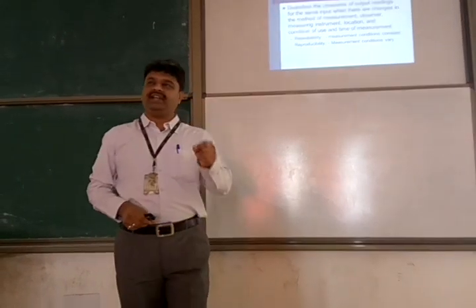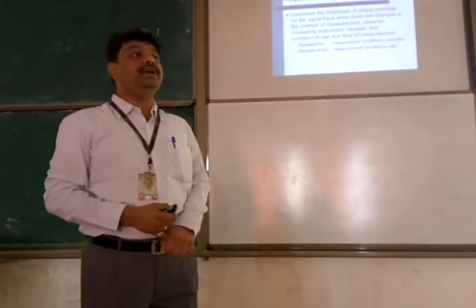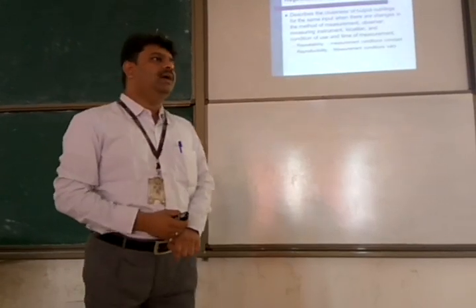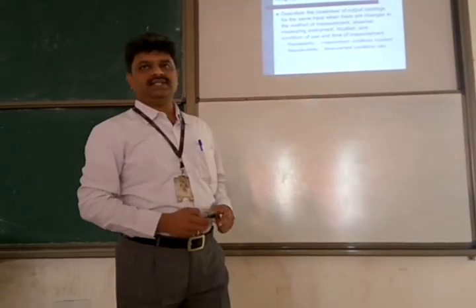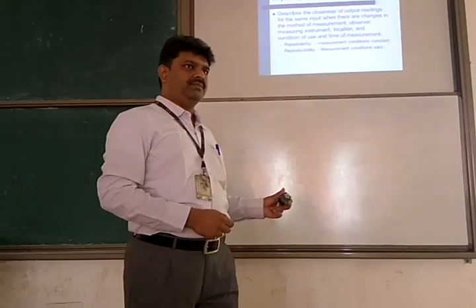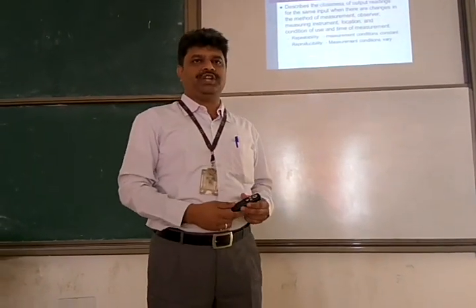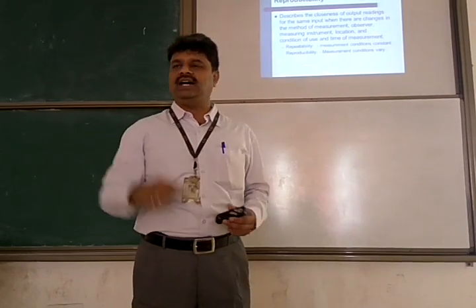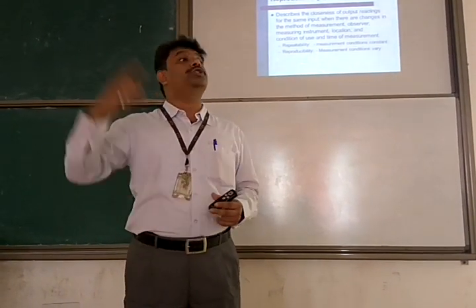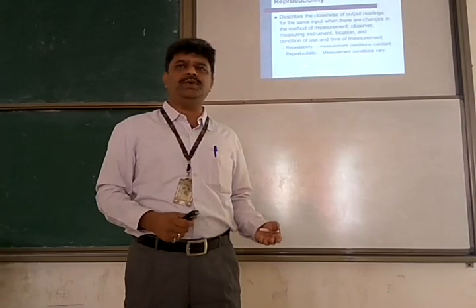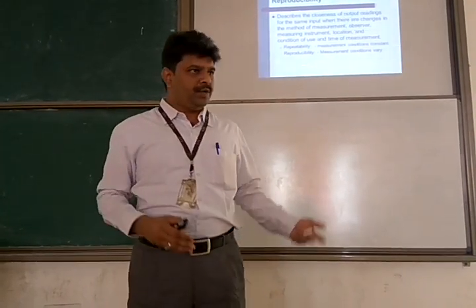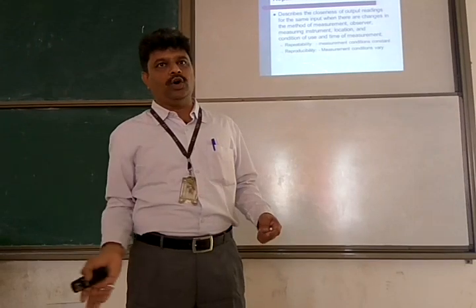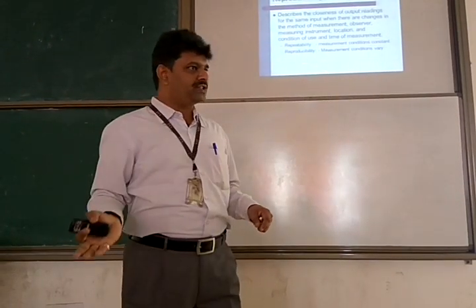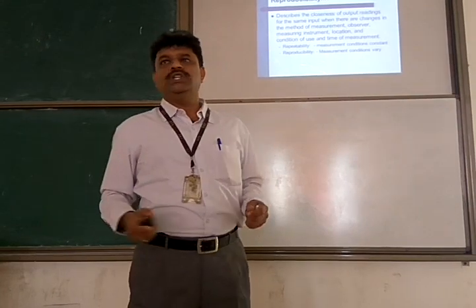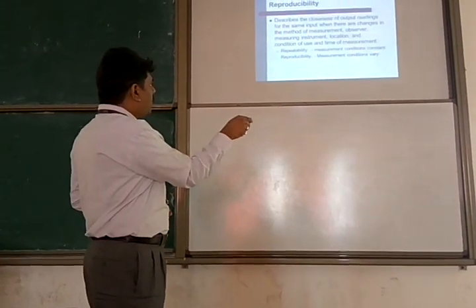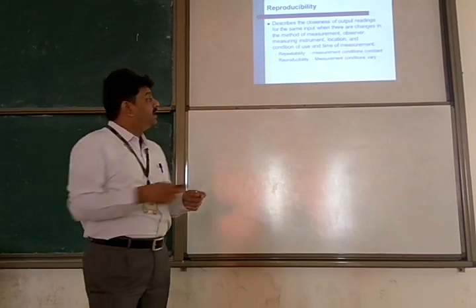I give a specific name to that term: reproducibility. Why is this important? Because I do some measurement here and calculate the precision. Then I go to Ooty and compute the precision there—it should be the same, even though here the altitude is low and there it's high, here humidity is high and there it's low, here temperature is high and there it's low. All conditions will vary, so repeatability is only good under very controlled conditions.